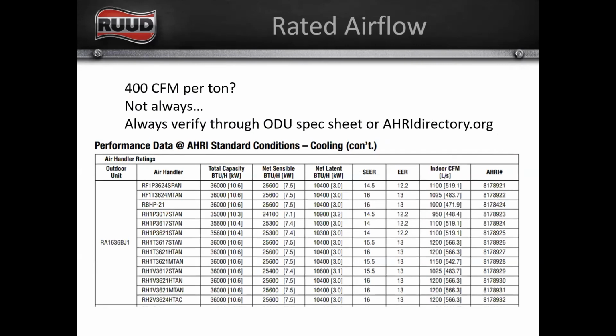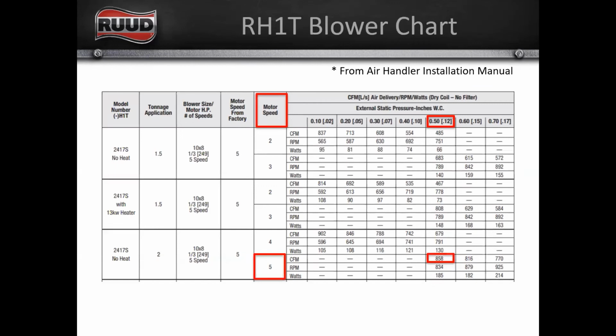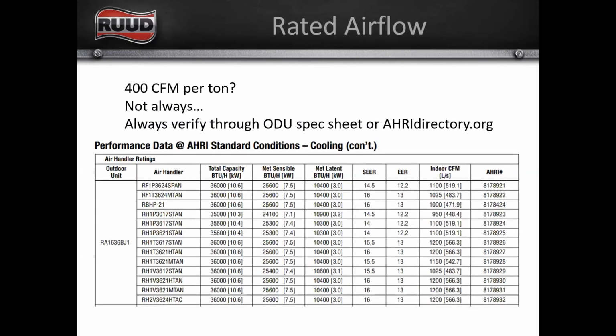Not yet. We don't know, right? At this point, we know how much air we're moving, but we do not know how much air this matchup calls for, right? I was taught, and I'm sure many of us, I think 58%, I think is what it was, of the people in here have been doing this for 10 plus years. I would wager that all of us were taught 400 CFM per ton. That is not necessarily the case, especially with newer equipment, right? So with newer equipment, we're typically moving anywhere from 325 to 425 CFM, or that's rated, right?